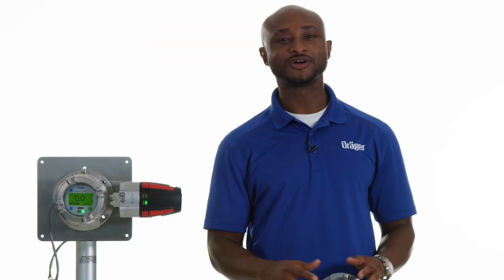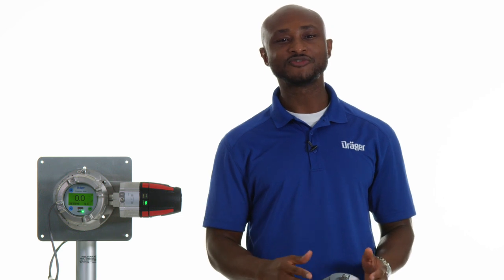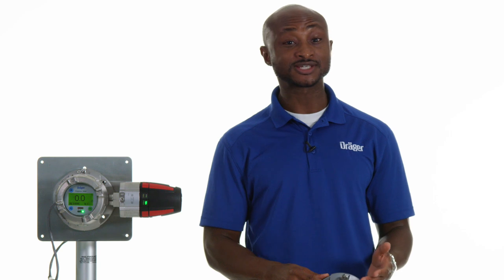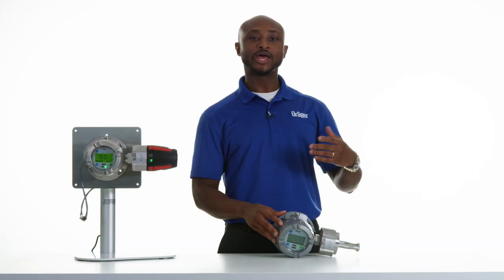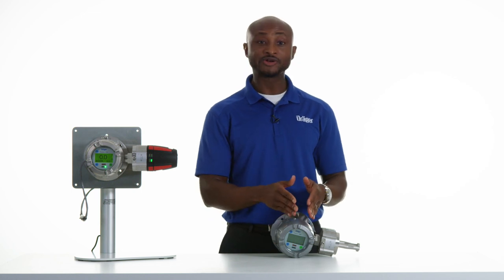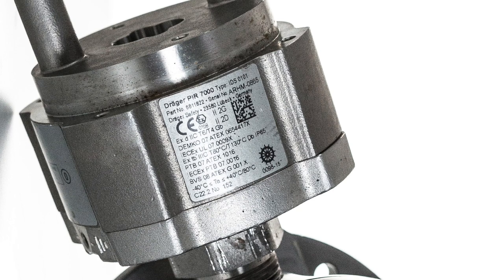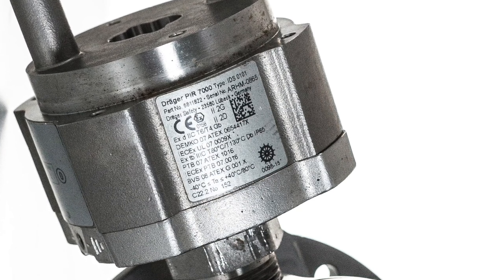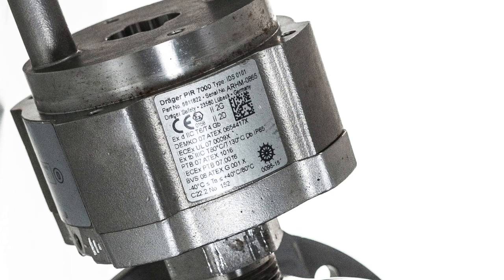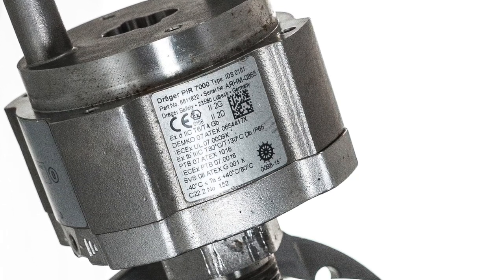The Polytron 8700 comes equipped with a customizable gas library which can be configured to measure over a hundred different explosive gases and vapors. The available remote sensor housing allows you to install the transmitter up to a hundred feet away from the sensor. The UL-approved housing allows the Polytron 8700 to be used in Class 1 Division 1 hazardous areas, and it is also certified for SIL 2 applications.